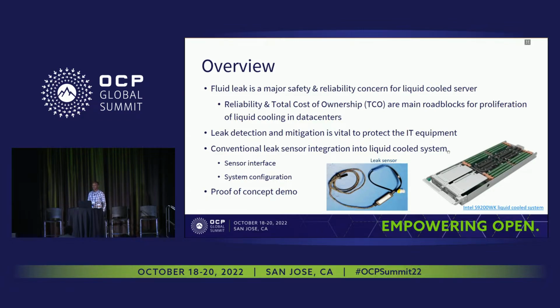with a leak. So the TCO, with the facility side of the infrastructure to get rid of the heat, depending on where this liquid cooling solution is implemented, on the geo and location. So that's a major concern. And also from the safety and reliability side, bringing water into the IT equipment, that's one of the concerns. So that's the area I'm going to be focusing on and some of the work we did.